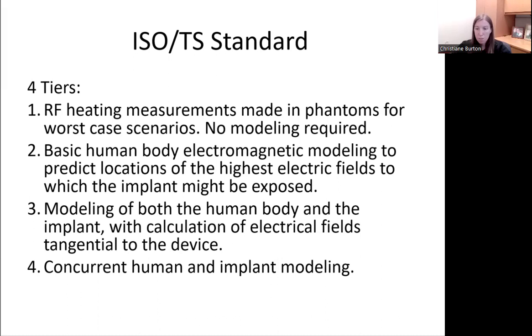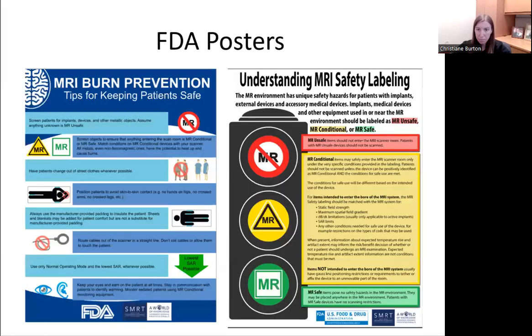ISO/TS 10974 describes similar tiered procedures for evaluating gradient-induced implant heating. Methods for measuring gradient-induced vibration of implants are also included. Here are two important FDA posters to keep in mind. The first one talks about MRI burn prevention, and the other one talks about labeling, which is very important. So please go check those out on the websites.